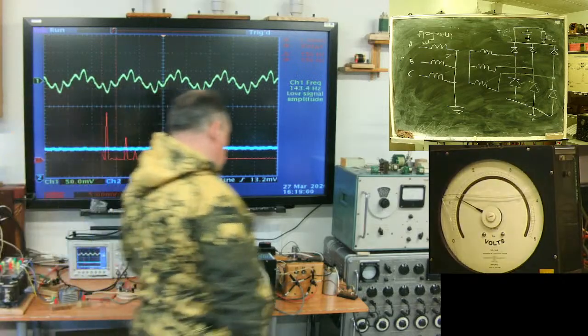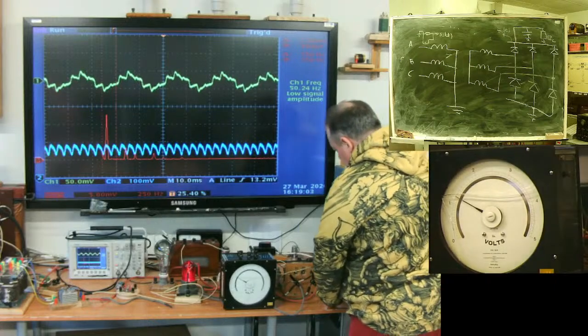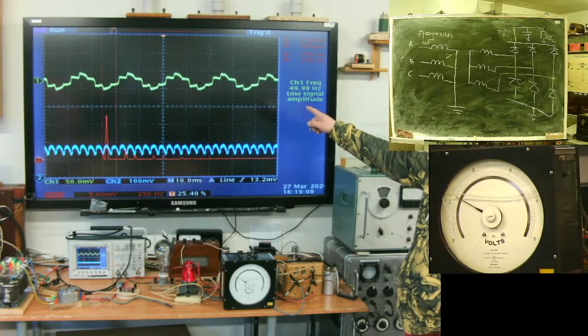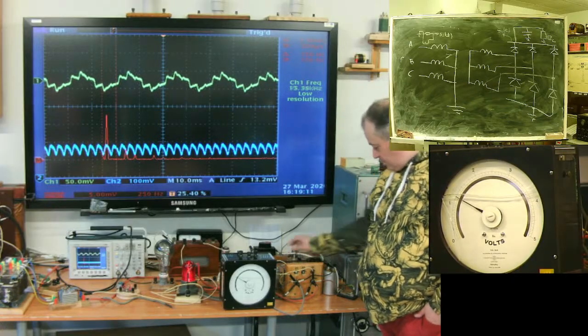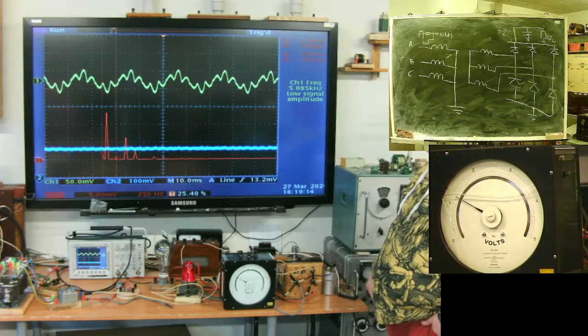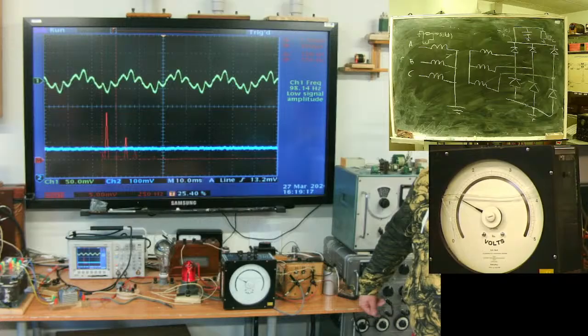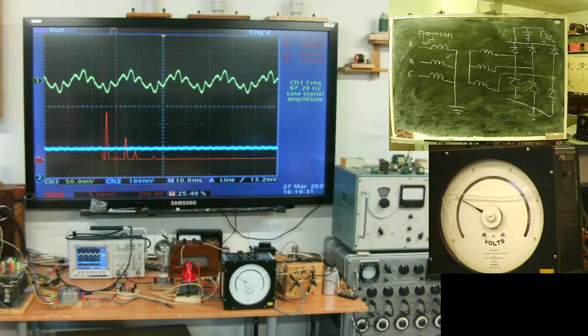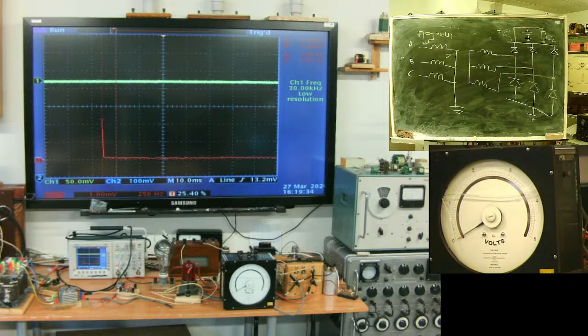Voltage. Delta without the filter. See improvement. Small filter, good filter. Here what we will see on primary side when transformer is with delta connection. Delta connection improves quality, let's say, reduces impact on network.